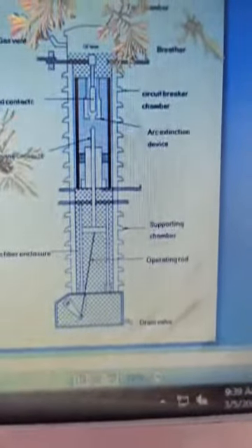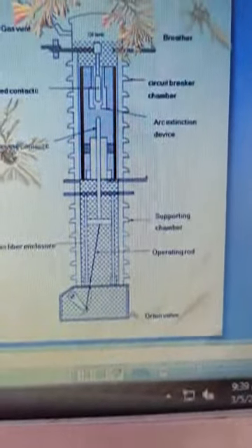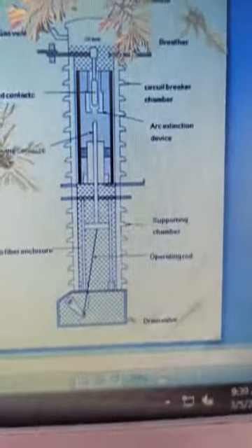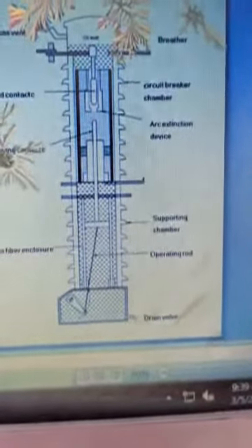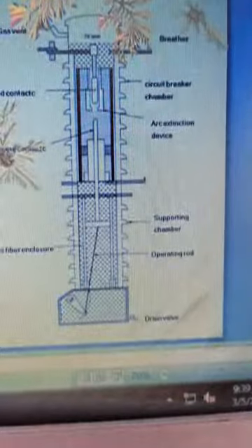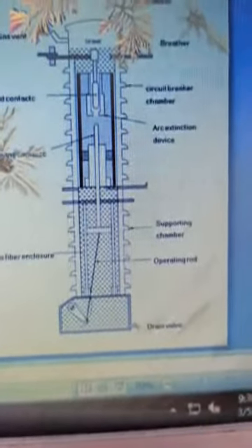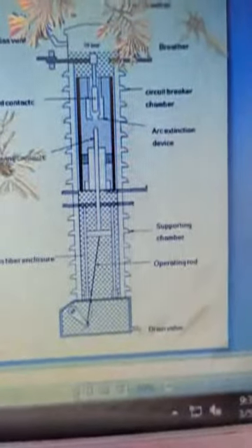The pressure buildup and flow of gases is influenced by the design of the arc control device and the speed of contact travel. The energy is liberated by the arc, and the gas flowing near the contact zone causes cooling and splitting of the arc. The contact space is filled with fresh dielectric oil.